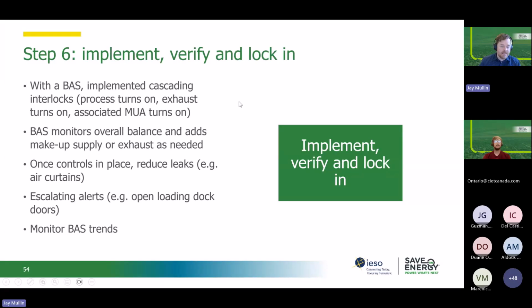And then step 6, implement, verify, lock in. So with a BAS, bringing in the BAS, they were able to implement cascading interlocks. They had it set up so this weld booth turns on, the exhaust turns on, the associated makeup air units turn on, and that all happens automatically. The weld booth turns off, the exhaust fan turns off, the makeup air unit turns off or ramps down appropriately.